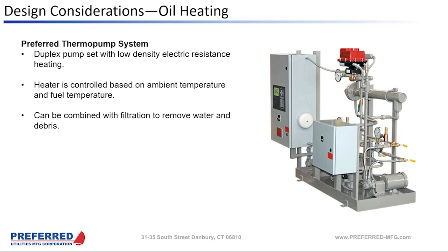Yeah, this is really the preferred, quote unquote, method that we see here in the Northeast. I mean, if I'm designing a system with an engineer, and we're concerned about cold fuel in any area, whether it's piping, whether it's in a day tank, or whether it's in the main storage tank, the most effective piece of that system is going to be to get a thermopump in there.